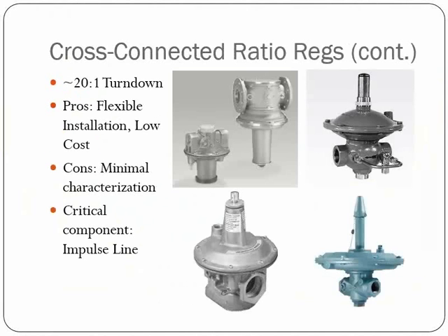These regulators will give you a lot more turn down than the previous inspirators. We're looking at approximately 20 to 1 turn down. The pros on these are that it's a flexible installation, and it's also relatively low cost. It'll be more expensive, of course, than the inspirator. There are a couple more components, but it's going to give you better turn down and control than the inspirator.